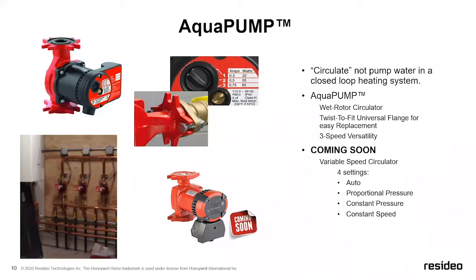But a couple of things that we do: all of our Aqua pumps, we have 3 different models, all of them are wet rotor circulators. And what that means is the motor, the shaft, and the impeller are all in one chamber that's filled with the system fluid. So as the water or antifreeze mixture moves through there, that's actually doing the lubrication of the pump itself. So there's no need to add grease, etc., for the maintenance on these.